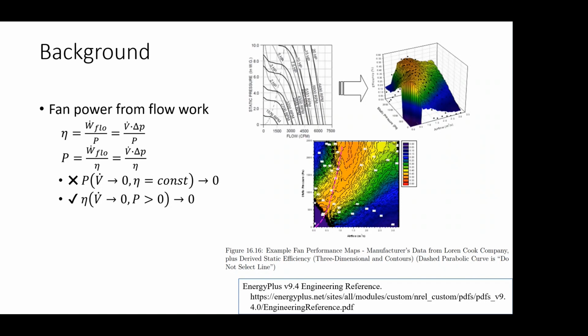Unfortunately, this is not correct. If we look at the power map, the fan's static pressure versus flow rate, we can see a 2 horsepower line crossing both the zero-flow axis and the zero-pressure axis. So we have either zero flow or zero pressure, but the fan is still consuming power.